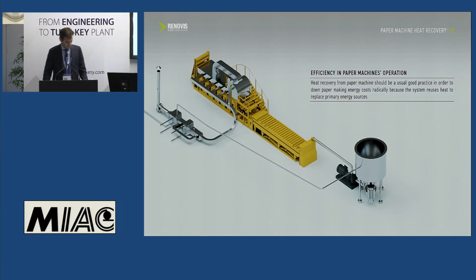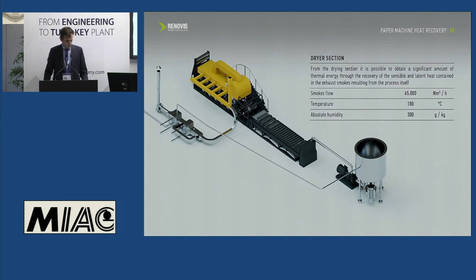I take this opportunity as a conclusion now to briefly tell you about another project that Renovis is developing, the recovery of waste heat from the paper machine. Heat recovery from the paper machine should be a usual good practice in order to lower paper making energy costs radically, because the system reuses heat to replace primary energy sources. From the paper machine drying section, it is possible to obtain a significant amount of thermal energy through the recovery of the sensible and latent heat contained in the exhaust smokes resulting from the process itself.